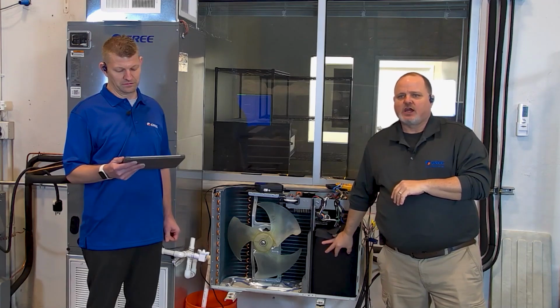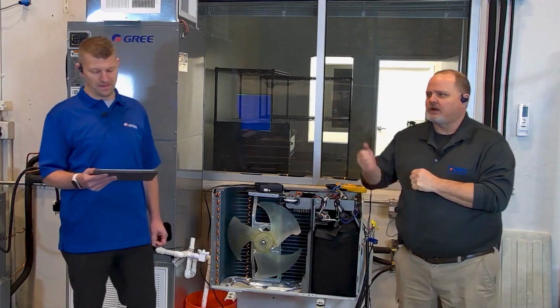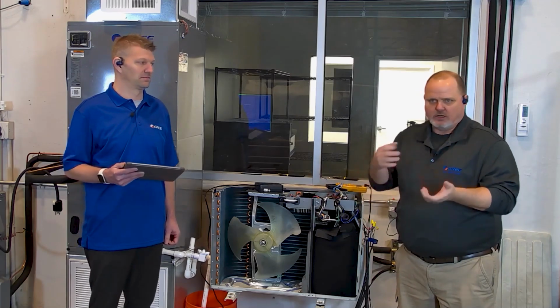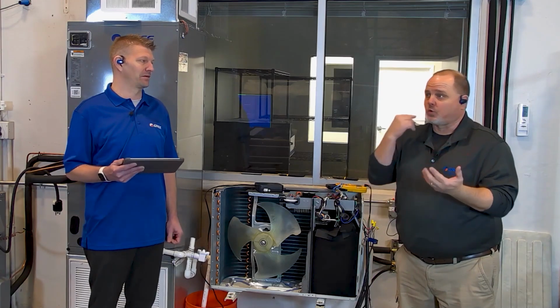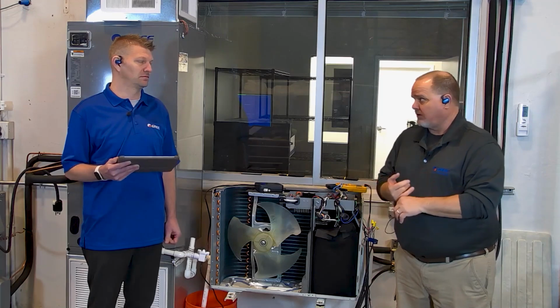You can peel this jacket back a little bit. If you have a heat gun, you can gently warm that compressor. That will help as well, because any liquid refrigerant that might be in that compressor, you're going to help get that to boil so you get it to come out of there. So a heat gun works great for working on heat pumps in cold weather. Not a torch. Not a torch.